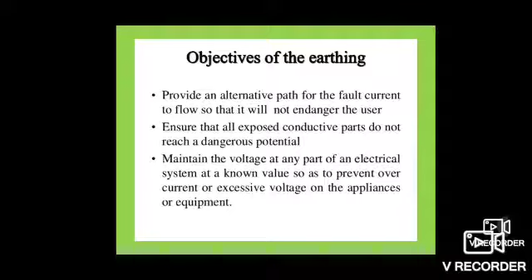See the purpose of earthing. It is used to save human life from the danger of electrical shock or death by blowing a fuse. That is to provide an alternative path for the fault current to flow so that it will not endanger the user. It is used to protect the buildings, machinery and appliances under fault conditions. That is to ensure that all exposed conductive parts do not reach a dangerous potential.